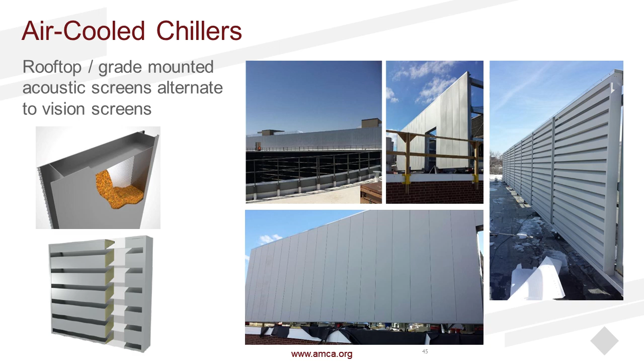Air-cooled chillers, but this could be any equipment up on a roof, can use either acoustic panels with a perforated inner shell and solid outer shell, or acoustic louvers. A lot of architects really love the acoustic louver look. Engineers like it too because if you have a piece of equipment, an air handling unit, an air-cooled chiller, or something close to that equipment yard wall, either up on a roof or on grade, it's got to breathe, and maybe you're closer than you'd want. So you want a low pressure drop acoustic louver. Architects like it because of the look, and there are a lot of different types available, including powder coated finishes.